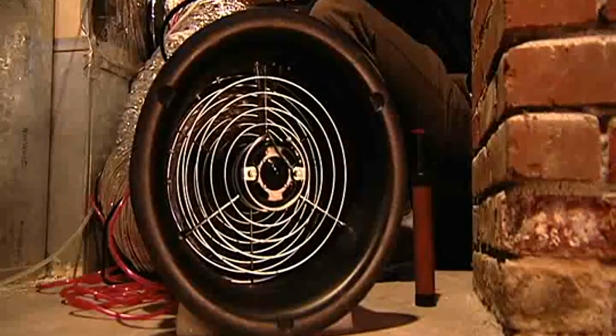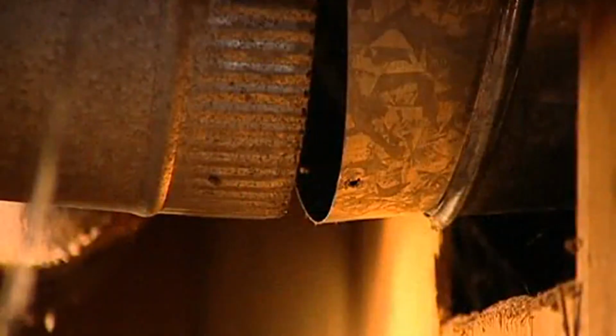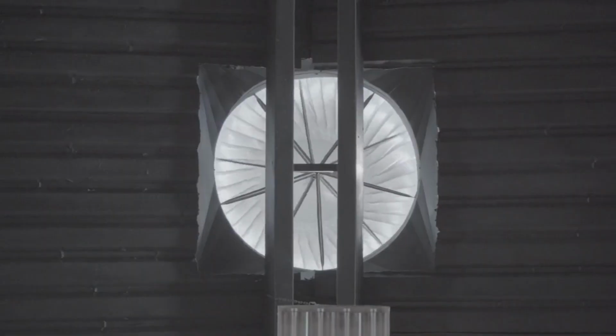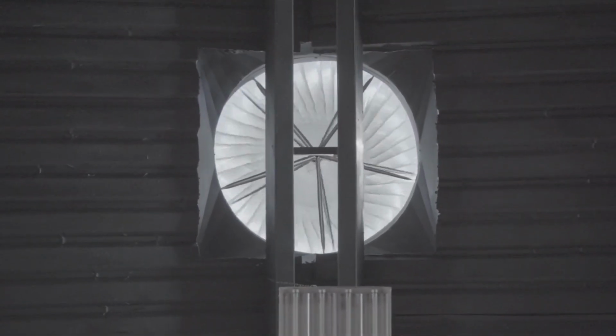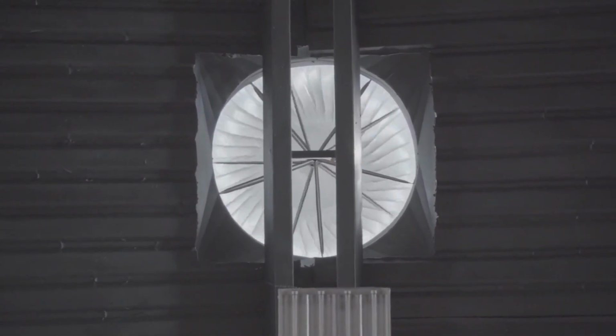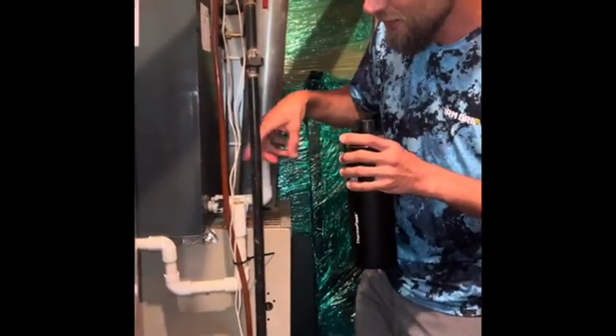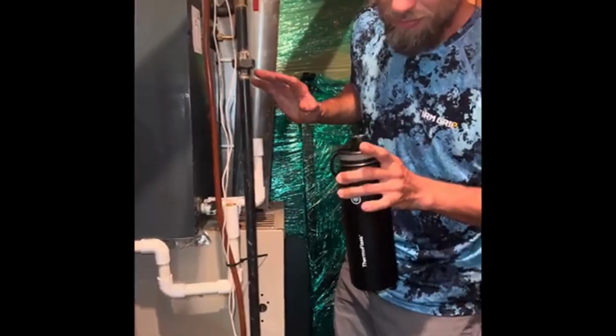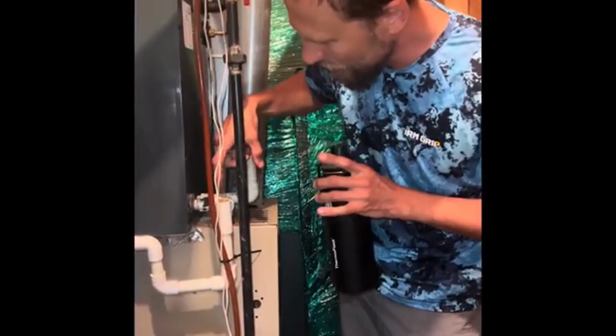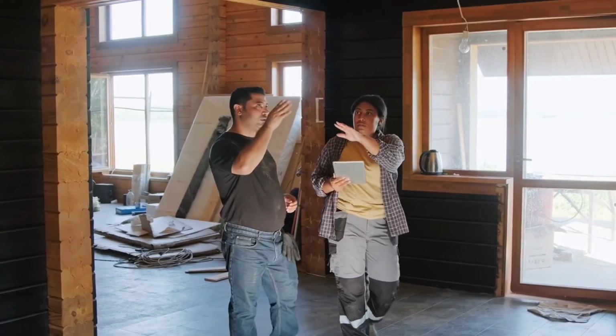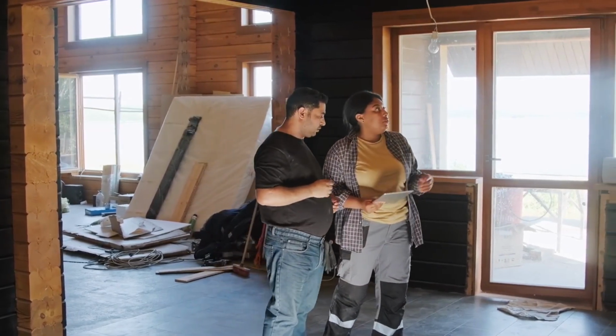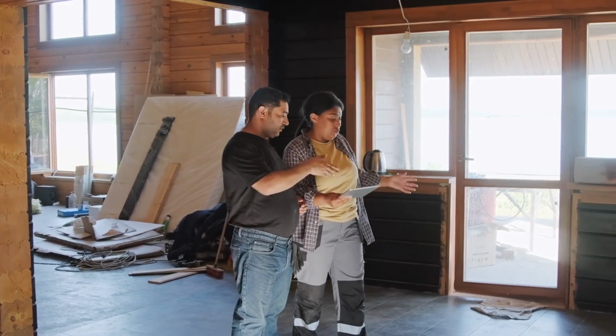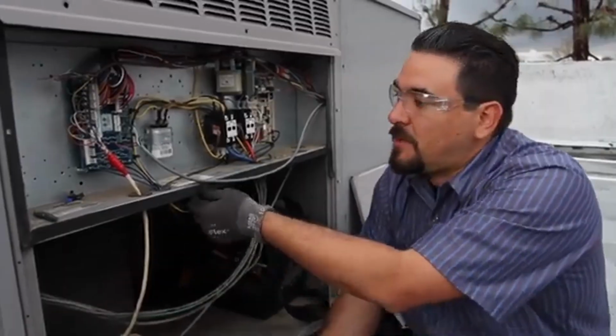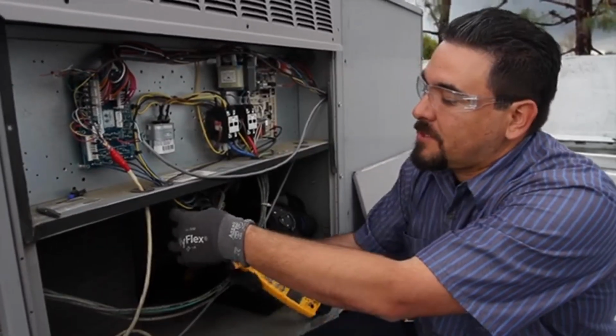Here's a pro tip. Before you approve an HVAC equipment replacement, ask the contractor about duct leakage testing. It's called a duct blaster test, and it pressurizes the duct system and measures how much air is escaping where it shouldn't. If they look at you blankly or immediately steer the conversation back to equipment, call someone else. A good HVAC contractor should be talking to you about the whole system, not just the box in your basement or on your roof.